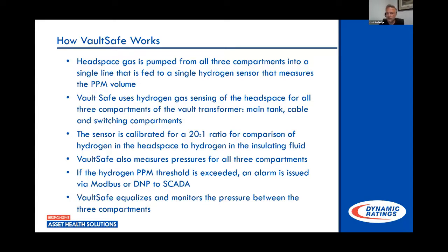That being said, it's also not homogeneously distributed instantly across that oil blanket. There's some things that have to happen with that hydrogen when it's produced in oil for you to detect it if you're putting a monitor at the drain valve of a main tank. So let's just assume that the fault that's occurring is on the opposite side of the transformer. So now we're depending on that hydrogen to be generated, and then whatever convection, and with these type of transformers, it's only going to be a natural convection due to heating of the coils and then passing through the radiators.